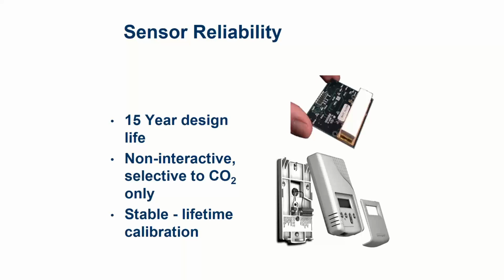Well, what happens is if people are hot and cold in a space, they start messing with everything they can. And they don't know that the CO2 sensor on the wall does not control temperature. They just know that there's a thing on the wall. Let's touch some buttons because I'm hot. And they'll pull the cover off, and they'll push that calibration button. It doesn't say calibrate, it's just a button. They push that button on the circuit board, and they just wiped out the reading on the CO2 sensor without having a can of gas connected to it. And then everything's all off. If there's a button, people are going to press it. If there's a switch, they're going to flick it. If there's a valve, they're going to open it.